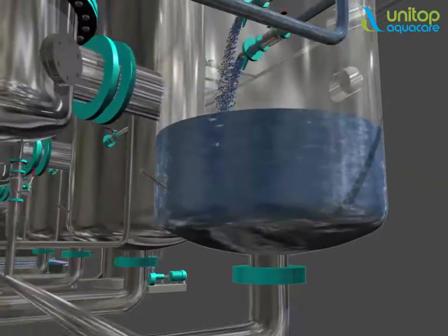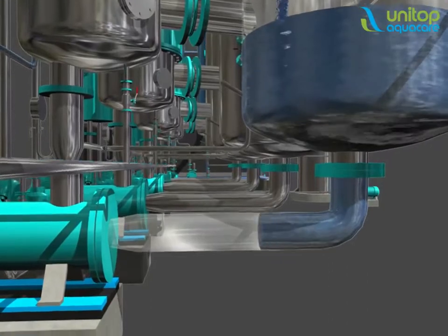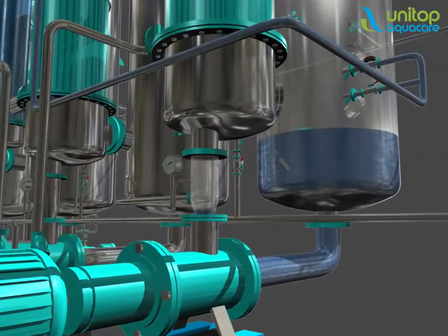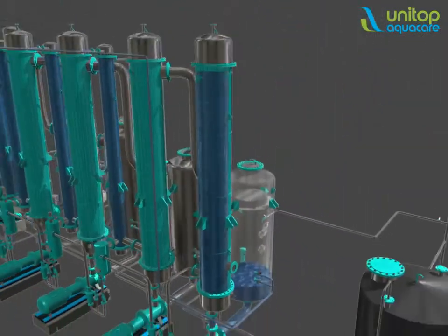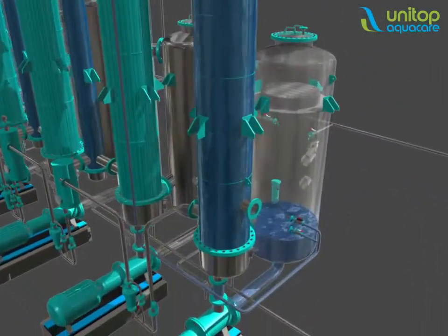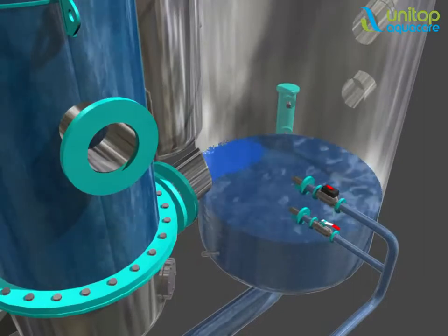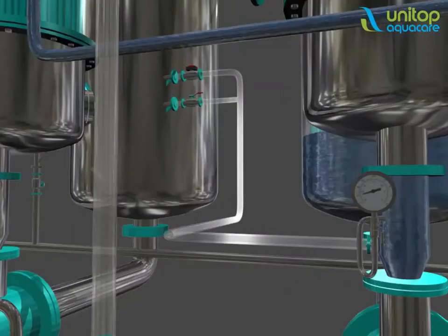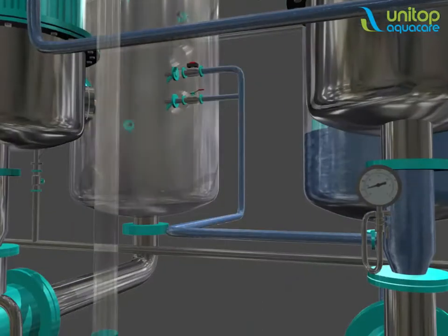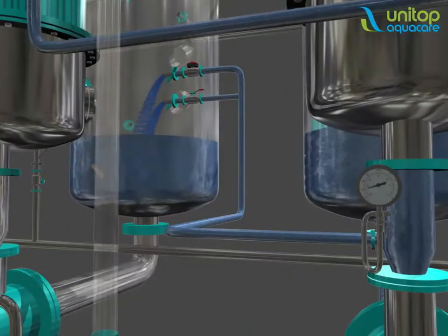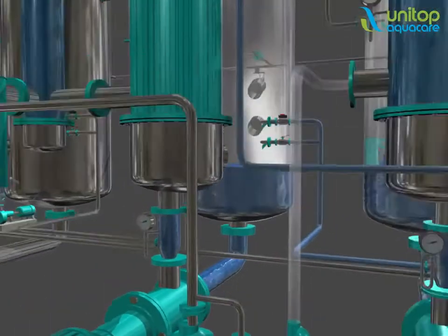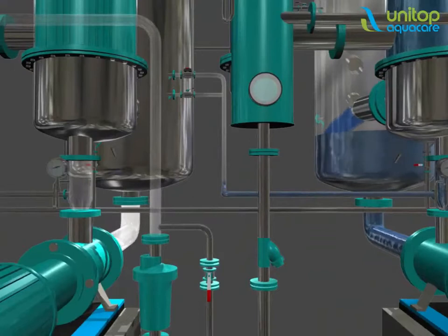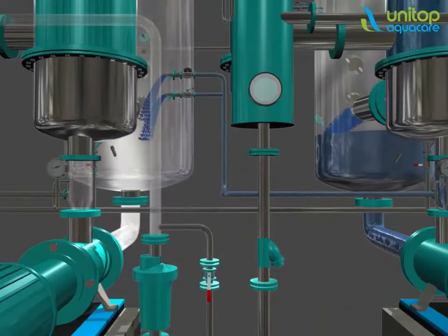The circulation through the heat exchanger is maintained at a high velocity with the help of a forced circulation pump, thereby reducing the possibility of scaling in exchanger tubes. The liquid gets transferred from the first effect to another on account of the pressure difference. The evaporation rates are adjusted in each stage in such a fashion that the desired concentration is achieved in the last stage.